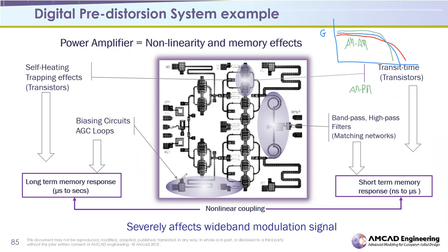You remember when we are doing pulsed measurements, my bias T's are very important because they need to be wideband. What does that mean? If I want to have a pulse going through this path here to the device, my bias network needs to have enough bandwidth to have a full pulse. Otherwise, it will cut my pulse like this, right? And this is not a pulse. So let's say my bias has 10 megahertz bandwidth to be able to have a pulse. And this is something that we can have easily.